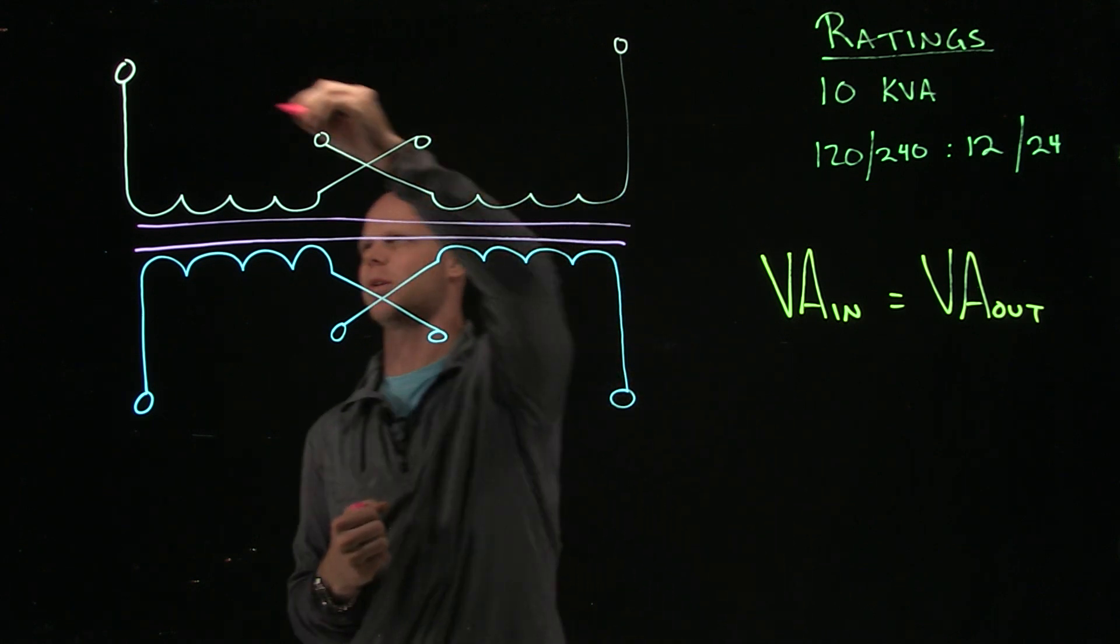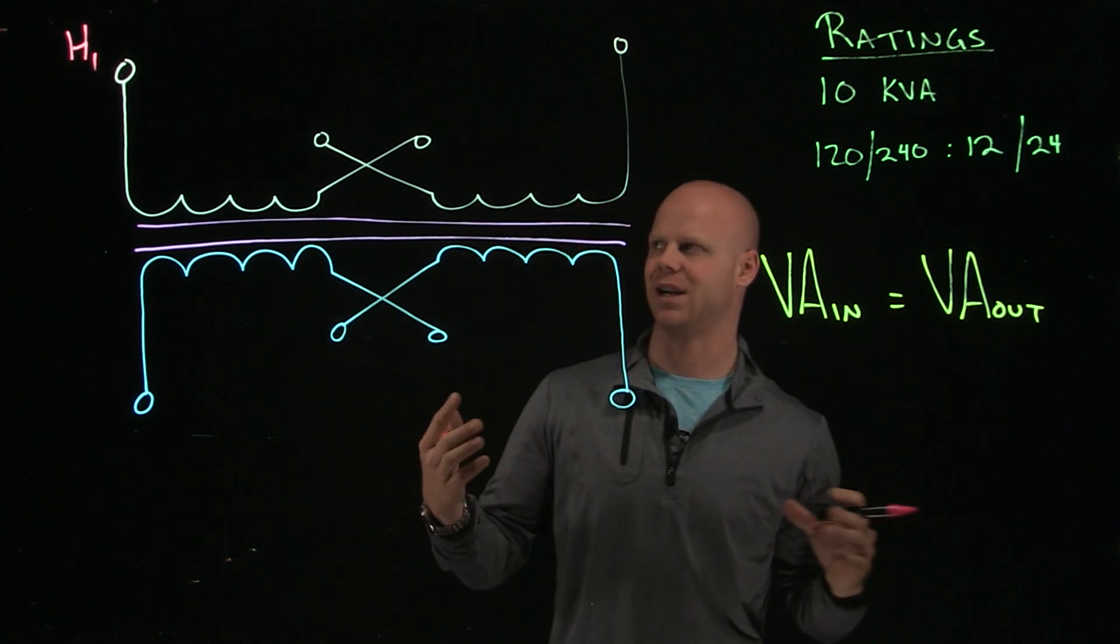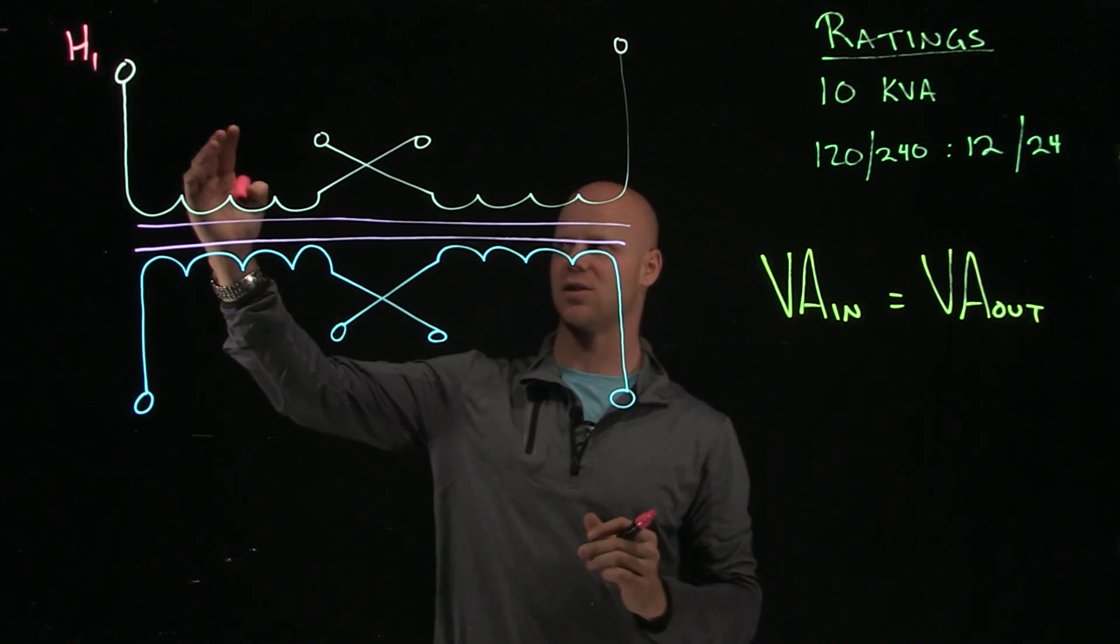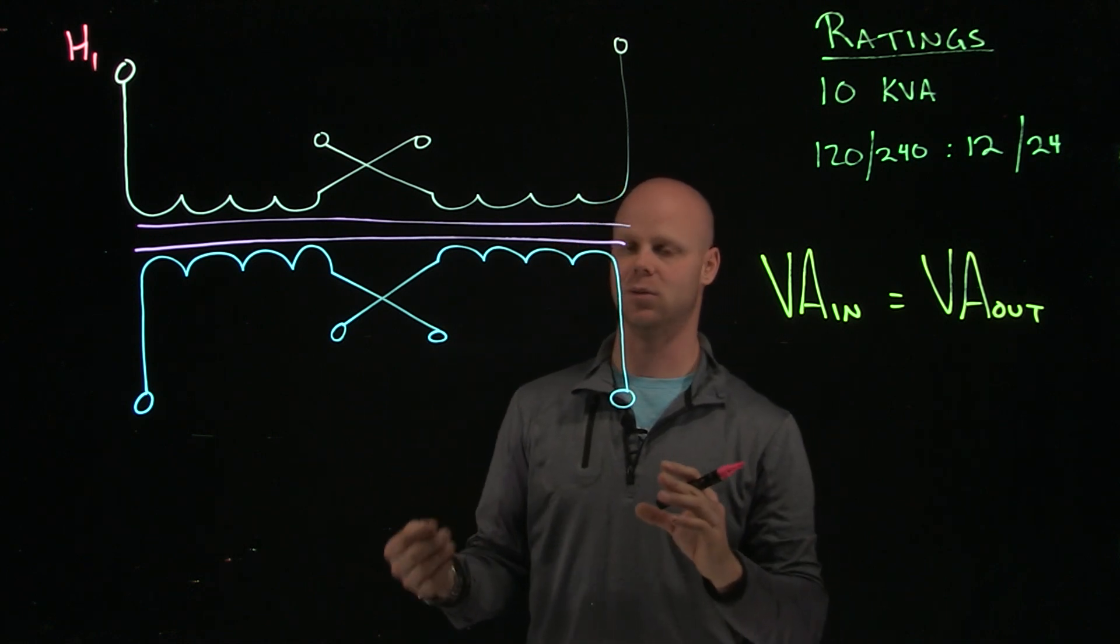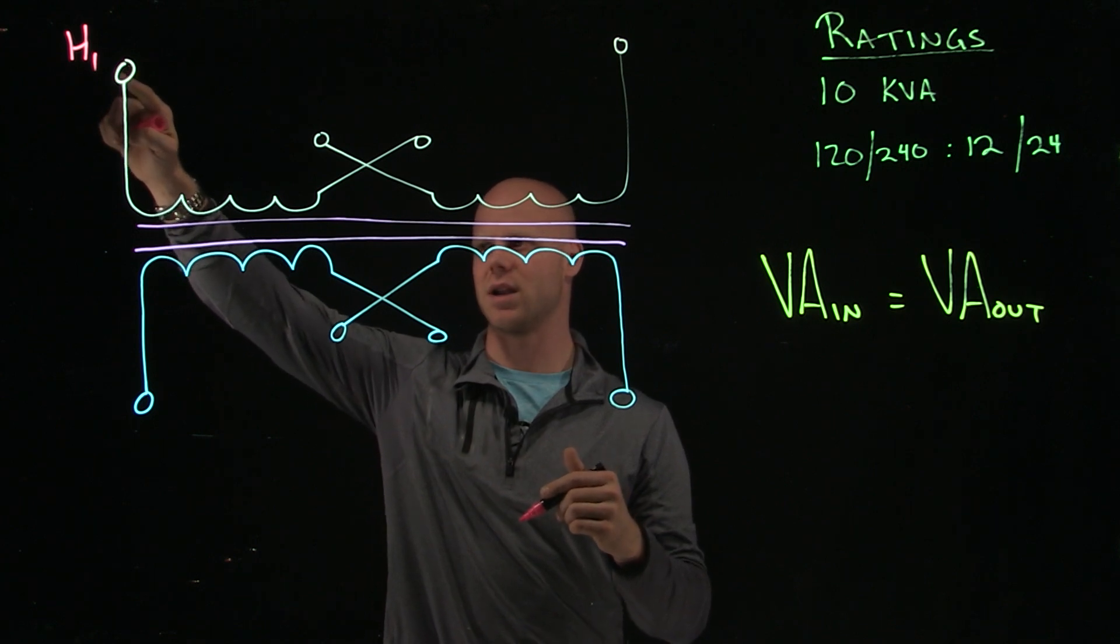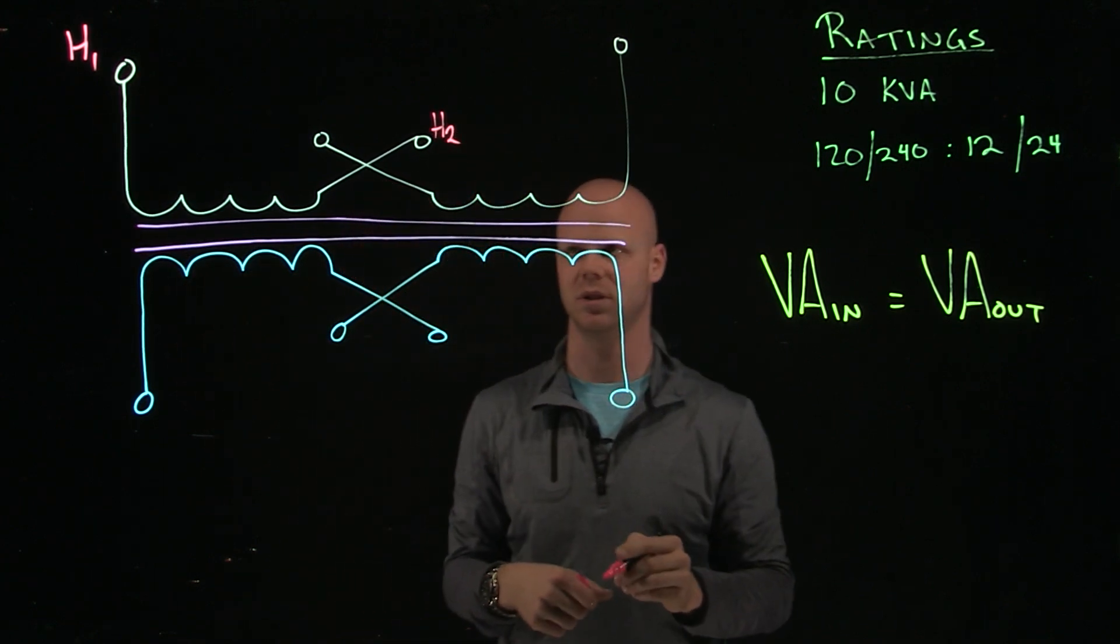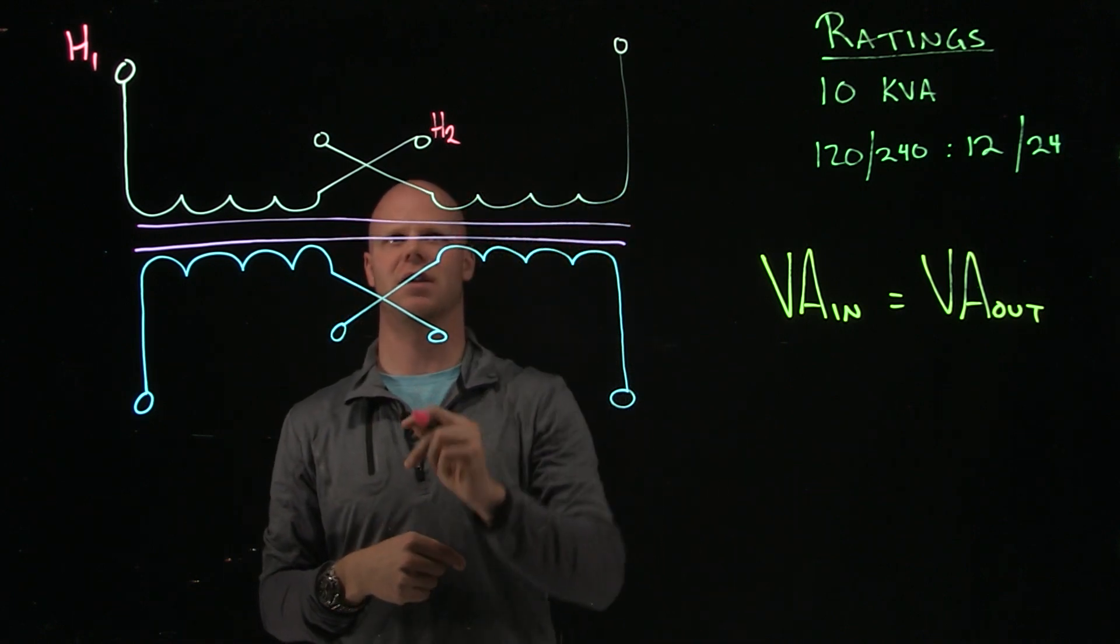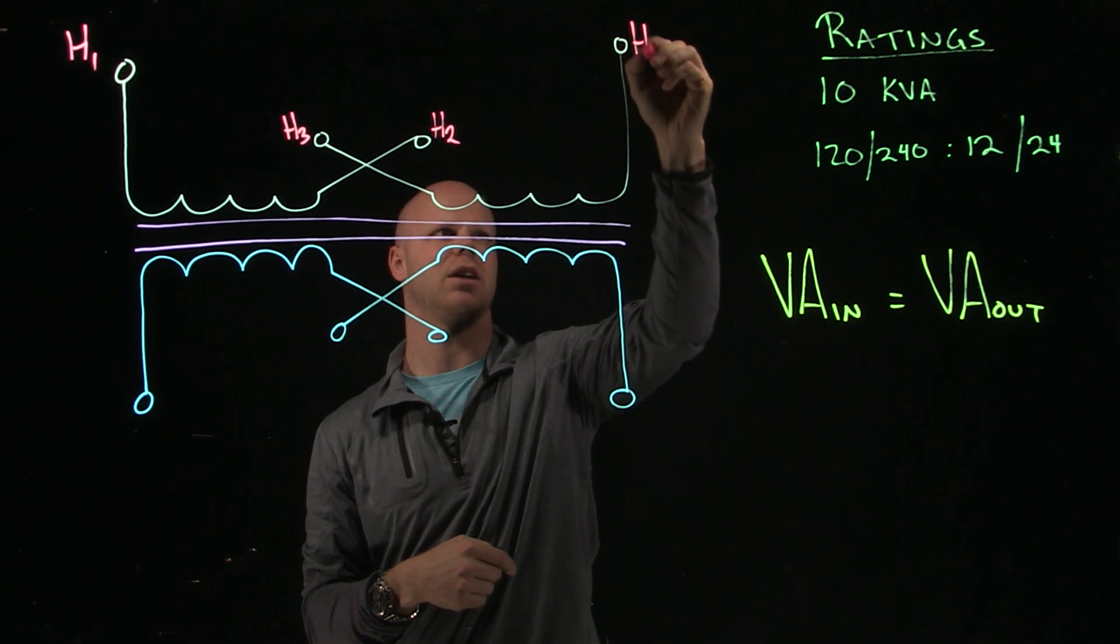So just for this example, I'm going to label this as my H1. Kind of an industry standard is that the H1 will always be the upper left. That way, if your terminals were missing, you would know that's definitively the H1. I could use an ohmmeter. But also if this is my H1, the other side of that winding has to be H2. So then if that's the other side of this winding, this will be H3. Here is my H4.